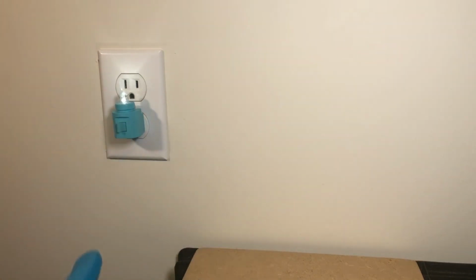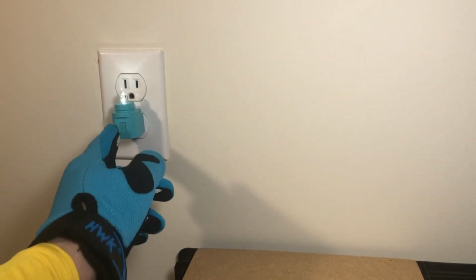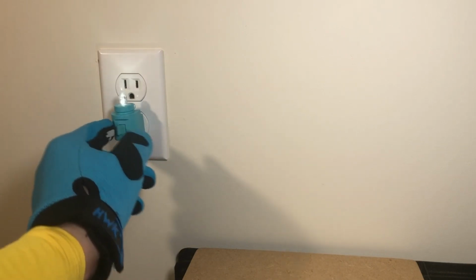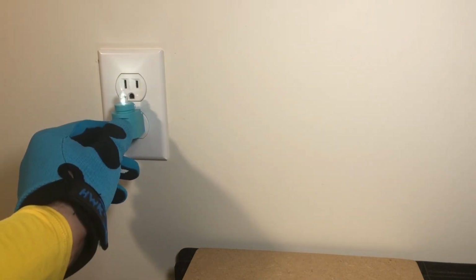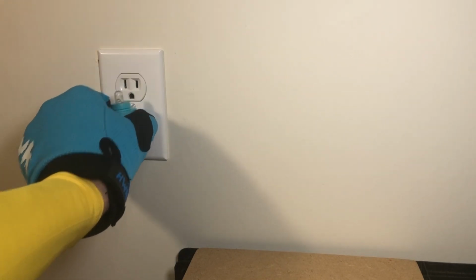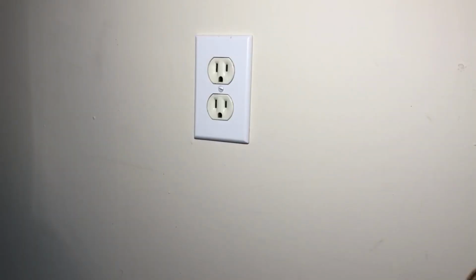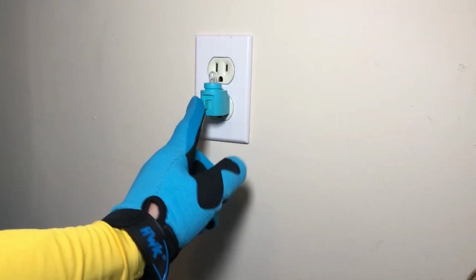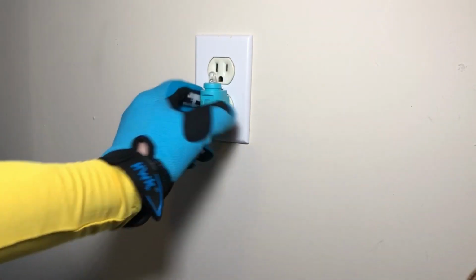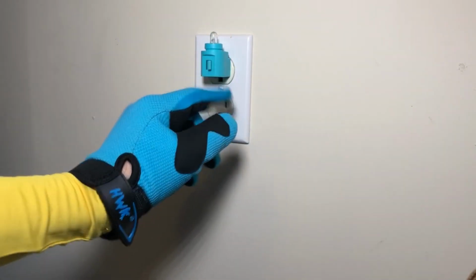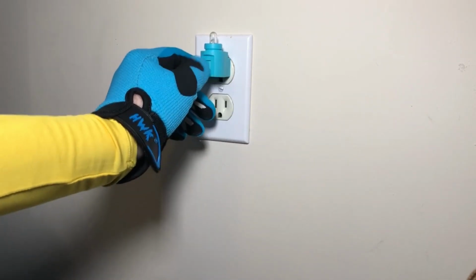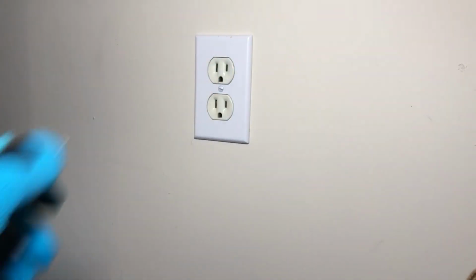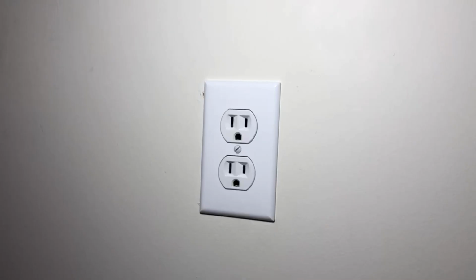Simply find yourself a known good device or appliance. It could be a lamp, nightlight, toaster, hairdryer, etc. First, test your lamp or appliance in a known good outlet and observe it working correctly. Then simply plug it into the suspected outlet and see if it works. If the test device works, you have your answer. The outlet has power. If the device doesn't work, return it to a known good outlet for one final test and be sure it works there. Using common sense and double-checking your test results will tell you whether your outlet is working or not.